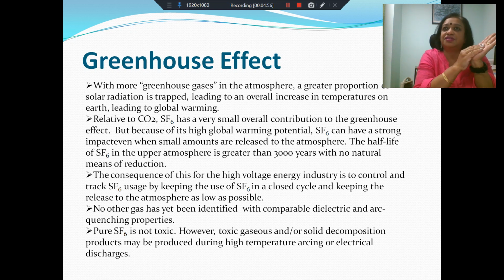Another concern is that SF6 has a very long half-life. That means small traces of SF6 once released to the atmosphere can continue to exist with half-lives greater than 3,000 years. So once you have done it, it will be there. And there are no natural means of reduction of SF6. For carbon dioxide, there are natural means of reduction. SF6 does not have any natural means of reduction. So even though we will be releasing very small quantities of SF6, that is going to be of potential danger. And therefore, the high voltage industry is under considerable pressure to control and limit the usage of SF6, and to make sure that when you use SF6, not even the slightest amount is released to the atmosphere.